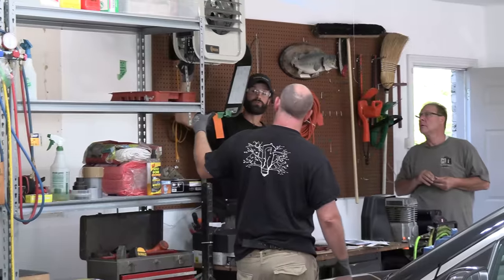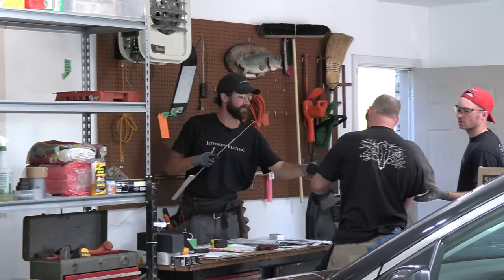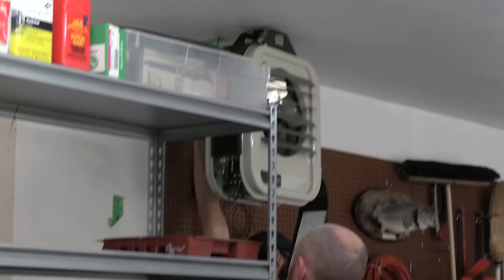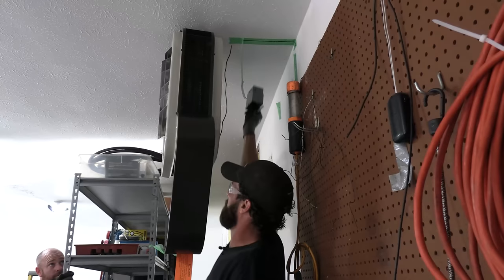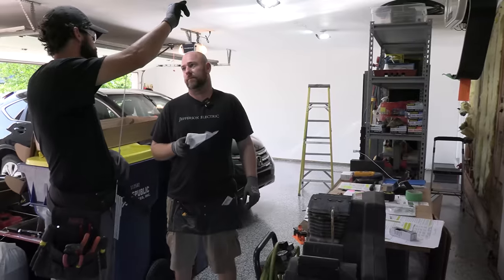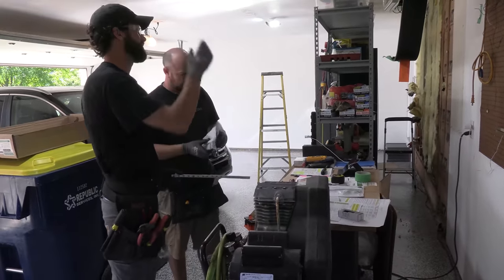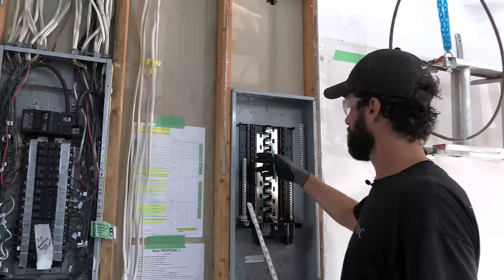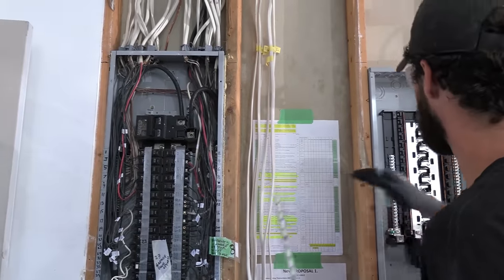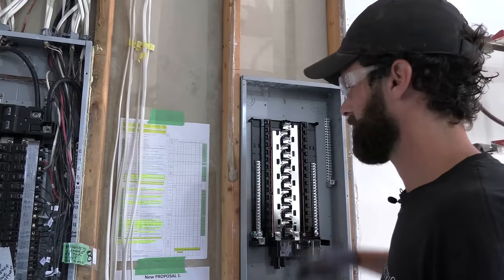Bruce, right up against the I-joist, flush — screw through the side, one down here, one up there. This remodel box has mounting screws that go right through there. Tom, do you want that orientation up against the I-joist, or do you want Bruce to pull out another remodel box turned sideways? Use these — they'll be more stout. Your wire will be continuous — don't make junctions in the box, come continuously into that heater. The Romex goes through the metal flex, through the box, which will give it a nice transition through the plate keeping it secured with the connector. We've elevated our ground bars from factory position up here and our neutrals won't have as much contest for space — we're in good shape at this elevation.